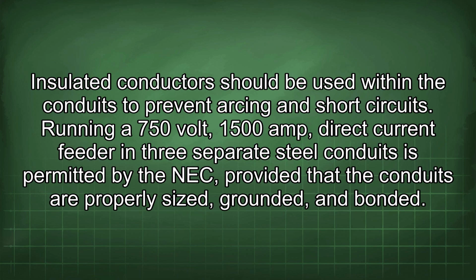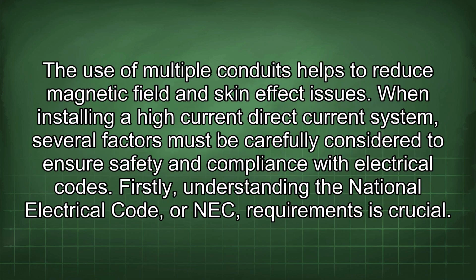Running a 750 volt, 1500 amp direct current feeder in 3 separate steel conduits is permitted by the NEC, provided that the conduits are properly sized, grounded, and bonded. The use of multiple conduits helps to reduce magnetic field and skin effect issues.